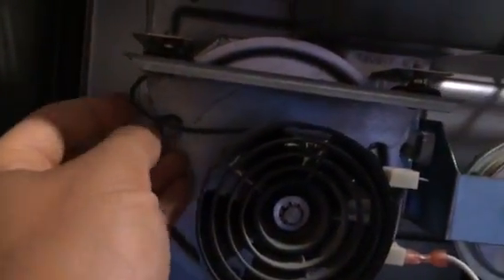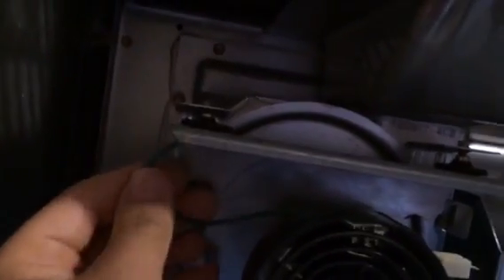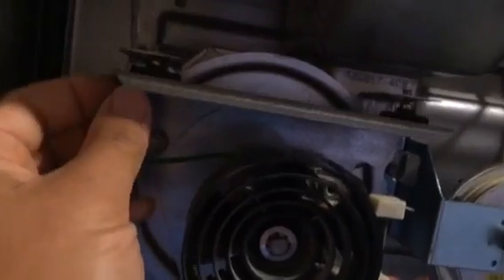So on this particular model furnace, the 58 PAV by Carrier, the venter motor or inducer motor is mounted on 3 different points, each point being a bit of a dampener at that screw point, so that literally will cut down on the sound being transferred to the ductwork and to the furnace. So I'm just removing those right now. I'll slide it out and I'll show you how I do that. Take note that there is a ground cable from the motor to this mounting point, so that serves as the ground for the inducer motor, and it connects right here.